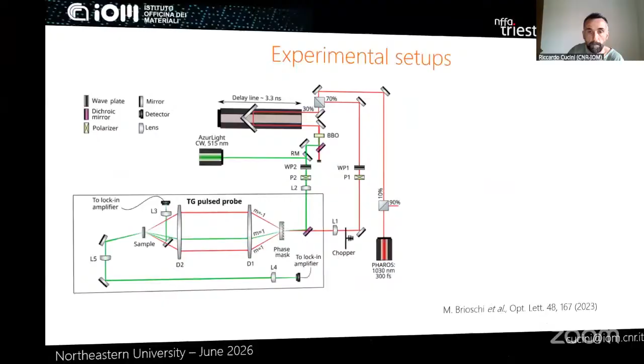So this is a standard experimental setup, the one that we have in our lab. As you can see, we use an ytterbium-based laser at 1030 nanometers. We split it in two here, and we have the pump and the probe. The probe is doubled in frequency. It can also be replaced with a continuous wave laser, so you can study the fast dynamics and the long dynamics by simply changing a mirror.